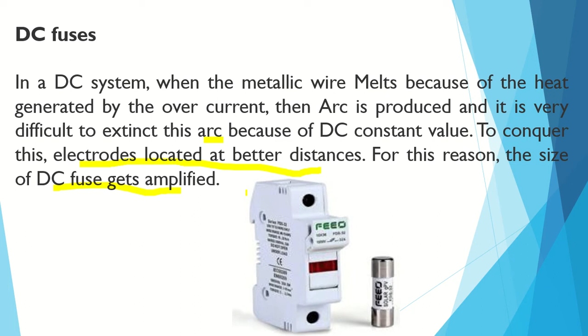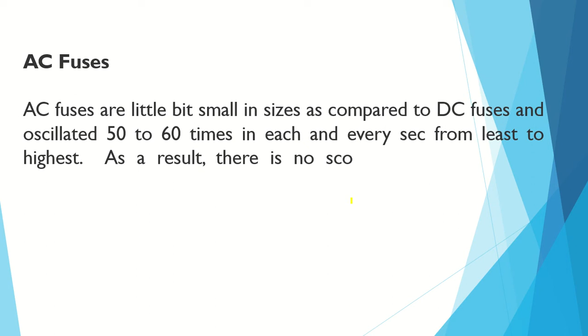Okay, next, AC fuses. AC fuses are a little bit smaller in size as compared to DC fuses, and they oscillate 50 to 60 times in each and every second from least to highest. As a result, there is no scope for arc generation between the dissolved wires. For this reason, they can be crammed into a small size. Okay, AC fuses are smaller in size as compared to DC fuses.